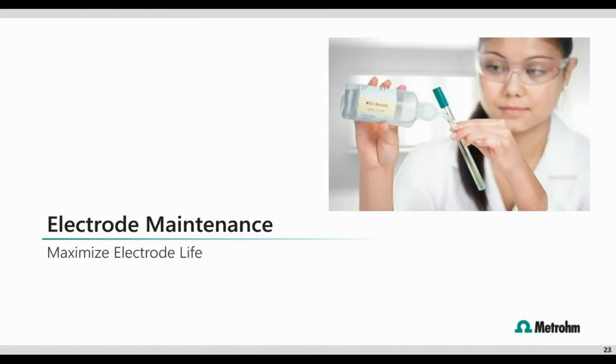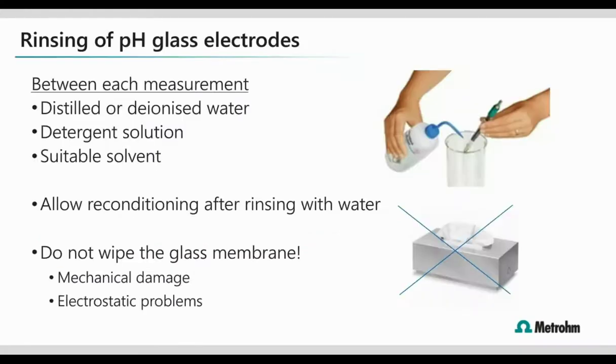So to maximize the life of your electrode, there are a few tips that I'd like to share with you that can help improve the electrode life. Between measurements, titrations, and when you're first putting the electrode into use, you should always rinse the electrode first with distilled or DI water. If that's not enough to clean it properly, say you're working with a really difficult sample, you can use a detergent or solvent depending on the kind of contamination. After that, always rinse it again with that distilled or DI water in order to recondition that electrode. The conditioning time can also depend on the cleaning time. So depending on what you cleaned it with, like if you used a solvent, that means you've likely stripped away that hydration layer on the membrane, and we need to allow it to condition in water a little bit longer.